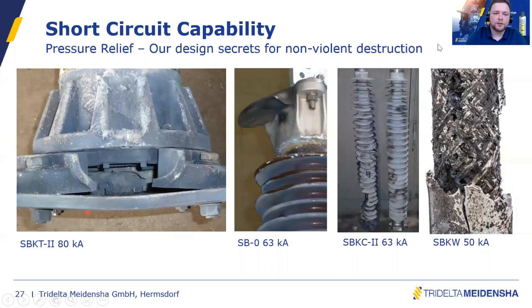And as Florent told you, we have different designs. For example, the tube design and the porcelain design for surge arrestors with gas volume. And we also have surge arrestors without gas volume, like the SBKC or SBKW type, which you see here in the two pictures on the right side.